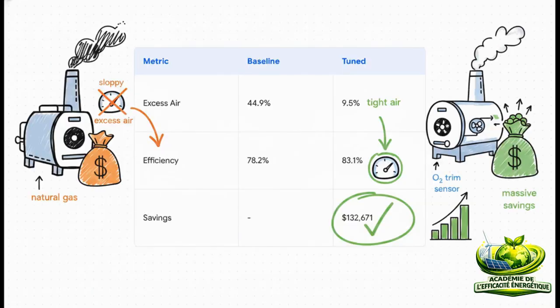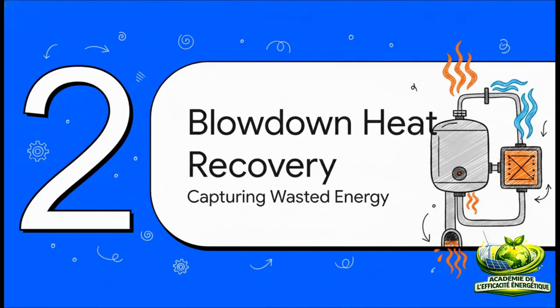peak efficiency. Let's put some real numbers to this, because the math is wild. Say you've got a boiler consuming 500,000 MMBtu of natural gas a year. If you tune it to drop that excess air from a really sloppy 44.9% down to a tight 9.5%, the combustion efficiency jumps from about 78 to over 83%. In this specific example, that optimization yields an incredible fuel savings of over $130,000 every single year. Honestly, it's no wonder the Department of Energy actually recommends O2 trim for any boiler burning more than $50,000 of fuel annually. Moving right along to Zone 2, heat recovery from your blowdown.